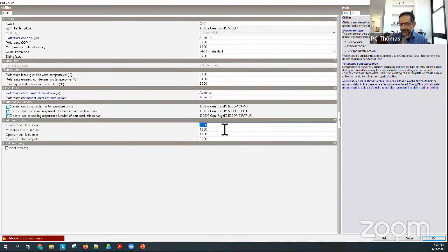If I run a simulation, I can look at each chiller and see where it's running at. I can see each fan in the air handling unit and see what it's doing. It's a variable air volume system, so you can watch the main fans go up and down. You can see what's happening in the VAV box. It's very, very powerful. But with that powerfulness comes a lot of flexibility and a lot of opportunities to provide garbage. Okay, so whatever you do, keep it simple, keep it really conservative, get practical numbers, because you can make your systems meet outcomes. We've done it. We worked on jobs where you do that.